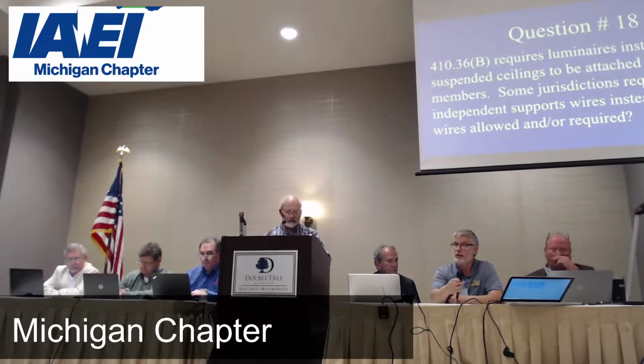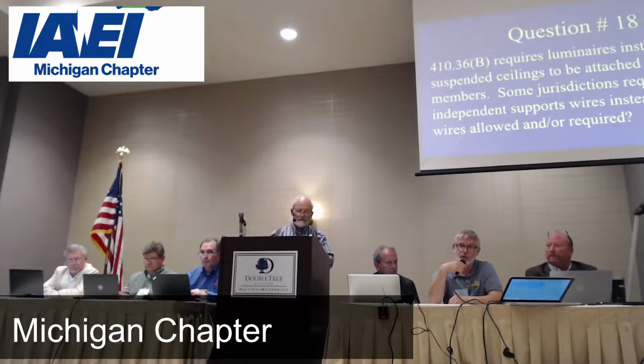Anything else on that one? Yeah, the extra wires for the luminaires come from the building code. If you're in certain seismic areas, you may have to put wires on the luminaires to hold them up. That's usually not what you would find in Michigan. We don't meet the seismic requirement for those, but that is a requirement in some areas that you have separate supports for your luminaires. Sometimes it's 2 corners, sometimes it's the 4 corners, it all depends on where you're at. And I know there are some jurisdictions where the building departments are making them put them up because the fire department wanted them. But that's of course a different color, so, but if Scott's right by the electrical code, they're not required.